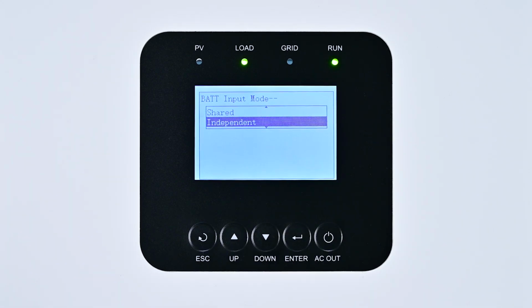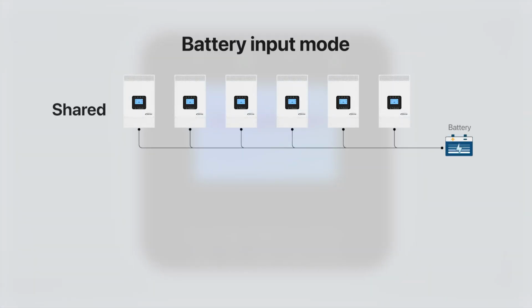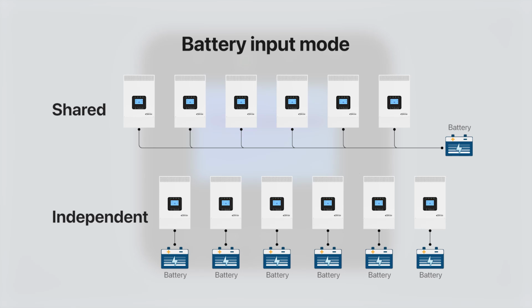In this section, you'll find two options for battery input modes. Shared. Independent. The shared option indicates that all devices in the three-phase setup use a single shared battery bank. The independent option means each device in the three-phase arrangement connects to its own battery bank, or each phase is connected to a common battery bank. It's crucial to ensure that the battery input mode setting corresponds with the actual connection method of the battery bank. Incorrect settings can lead to device damage.